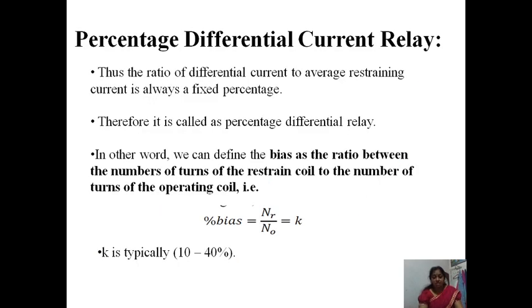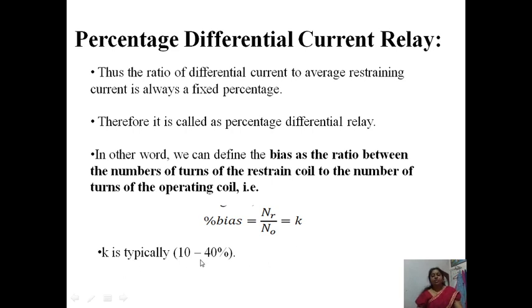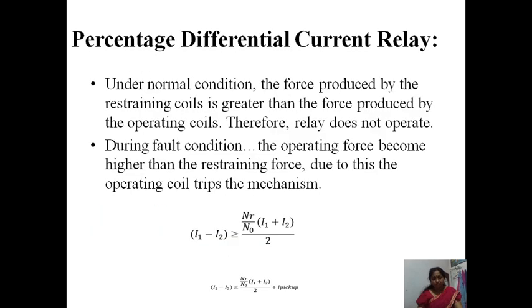Thus, the ratio of differential current to the average restraining current is always a fixed percentage — therefore it is called a percentage differential relay. The bias is defined as the ratio of the number of turns of the restraining coil to the number of turns of the operating coil: percentage bias = Nr / N0, represented as K, where K is typically from 10 to 40%. For a relay to operate, I1 minus I2 must be greater than (Nr/N0) × (I1 + I2)/2.